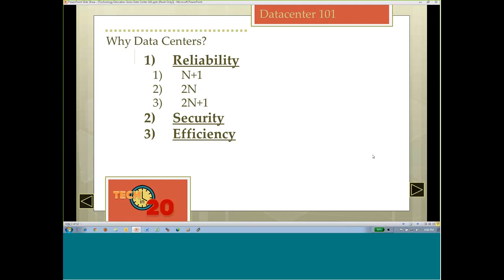One is called N+1, where N is the resources you have - in this case power - and the +1 means you have some extra. There's 2N, which means I've got the power that's required, and I double it. Keeping it in simple terms, N+1 is like if I have 10 kids over for a birthday party, I'm going to make 12 cupcakes so they all have one, just in case one or two extra show up. 2N means I would have 20 cupcakes for 10 kids, just in case a lot more showed up or there was a problem. And obviously 2N+1 means double it plus more.